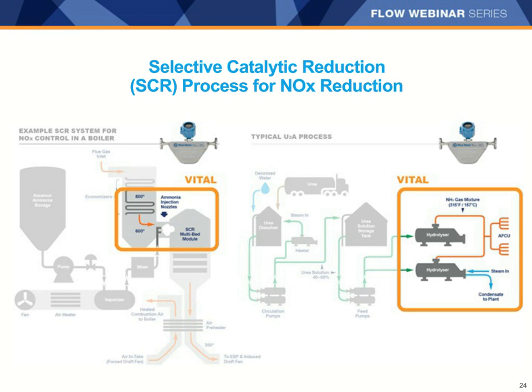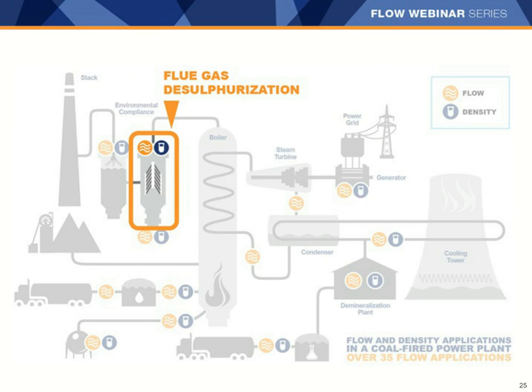Since the stoichiometry or chemistry is based on mass or mole weight reaction and not volume, it is better to control using a direct mass flow measurement. Coriolis meters can help with mass balancing, reducing ammonia slip, and measuring the ammonia concentration all in one device. In addition, due to their design that contains no moving parts, they can improve unit reliability. Next, I would like to talk about flue gas desulfurization.